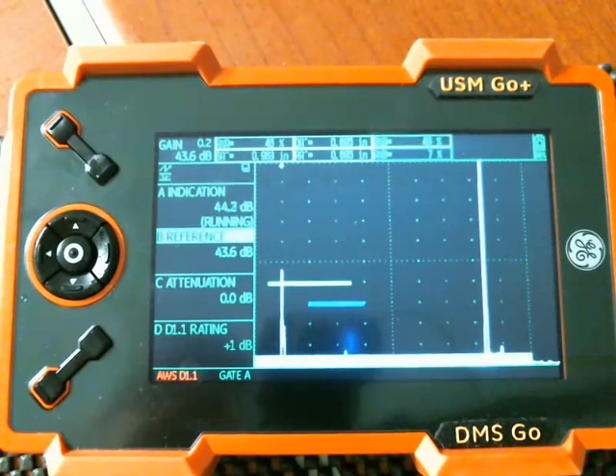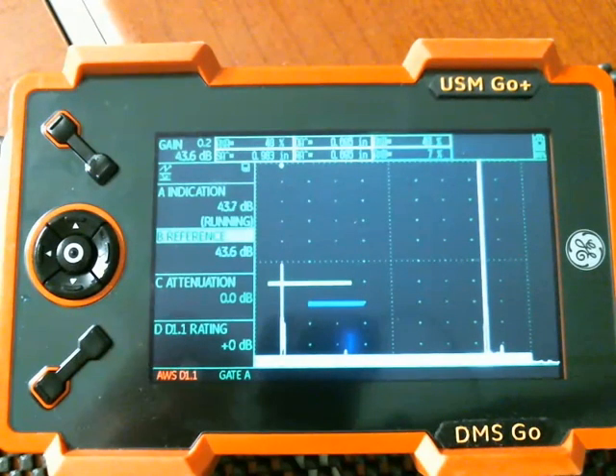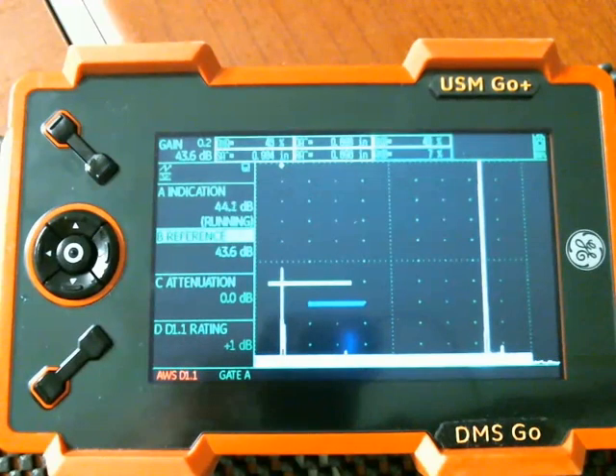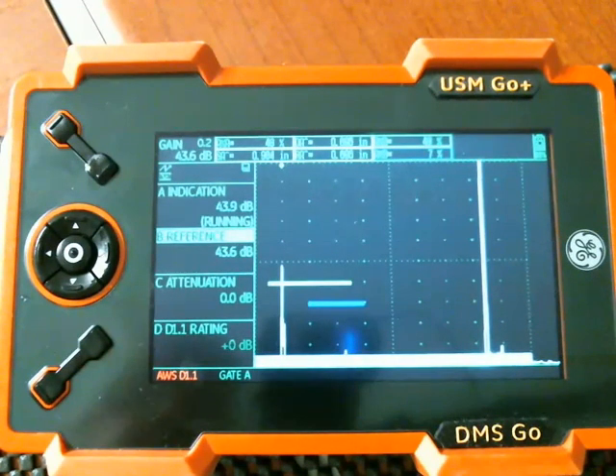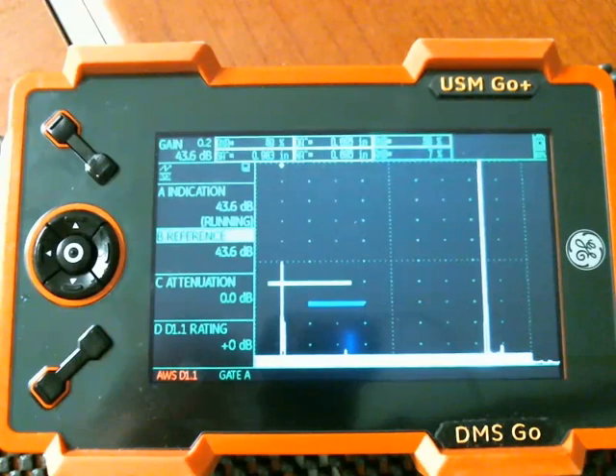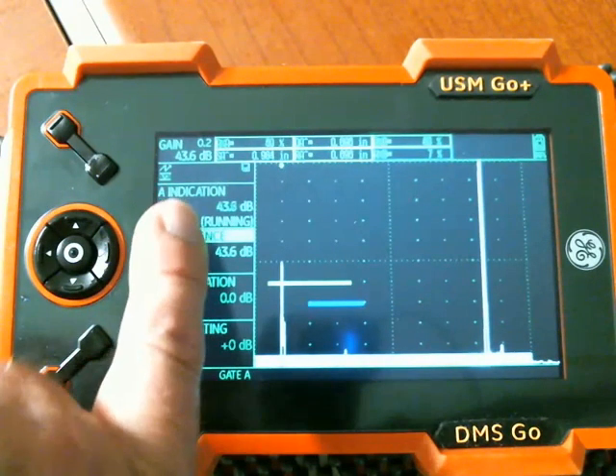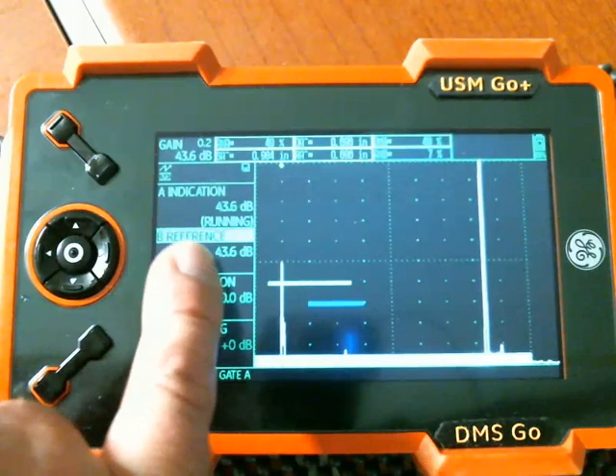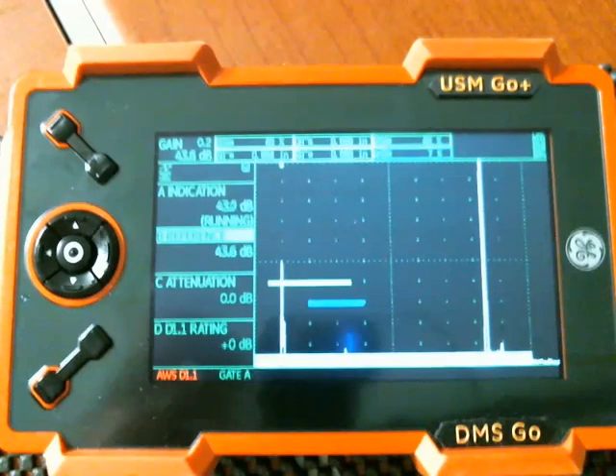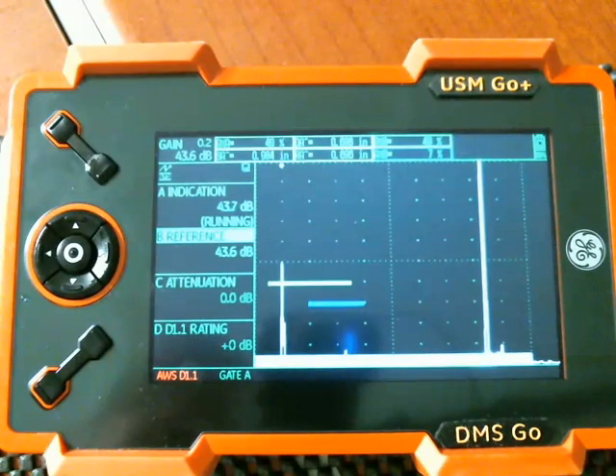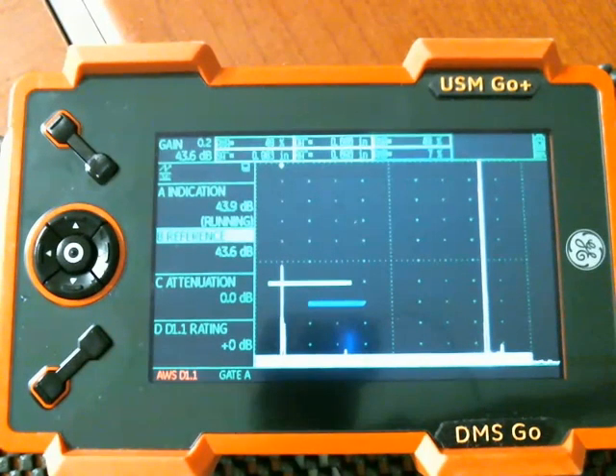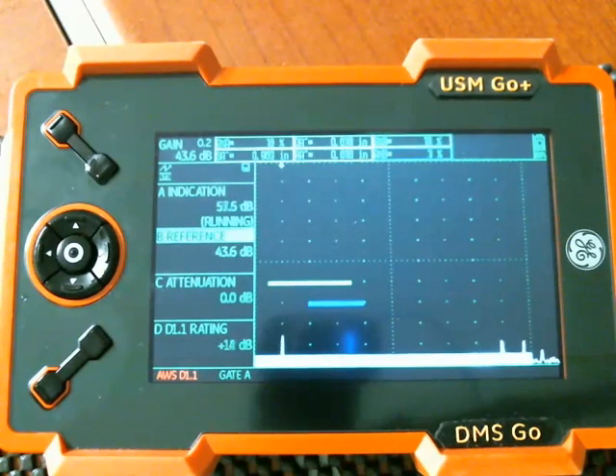So I have, I'm not going to go into a lot of detail on how the AWS method works. There's lots of information published on how this method works. But you'll notice I'm on the same hole. The gain to get a 50% echo matches the reference gain more or less. The C and D are coming right in at 0 dB because I'm at the same distance and the same sensitivity.